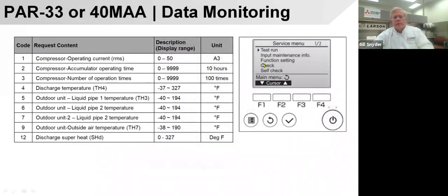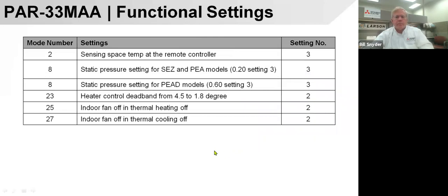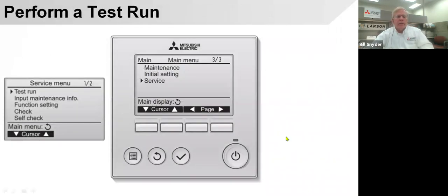This also has some test run and some function settings. You can go in there and see what the voltages are, what the temperatures are. You can see that all through going through the menu. So this particular control kind of helps you do some troubleshooting as well. You can change things like static pressure and all on the indoor units by changing the setting numbers through this particular stat. Makes it kind of nice, kind of easy.